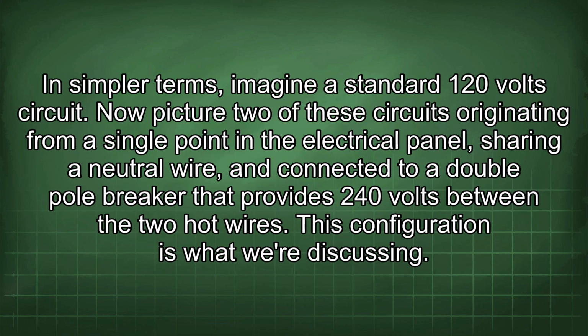In simpler terms, imagine a standard 120-volt circuit. Now picture two of these circuits originating from a single point in the electrical panel, sharing a neutral wire, and connected to a double pole breaker that provides 240 volts between the two hot wires. This configuration is what we're discussing.